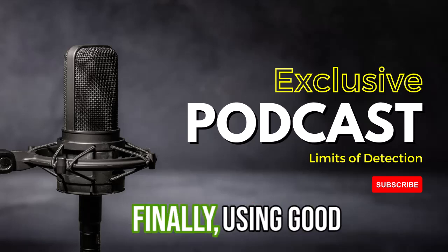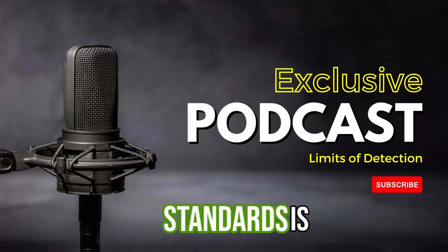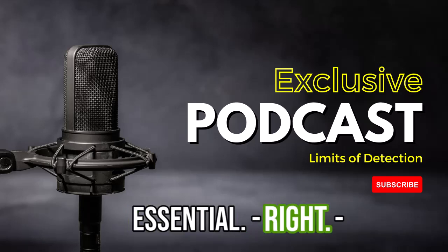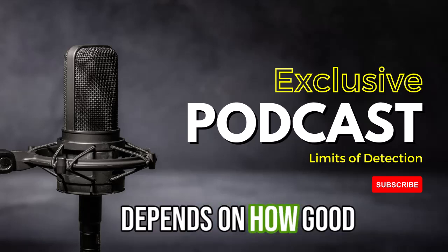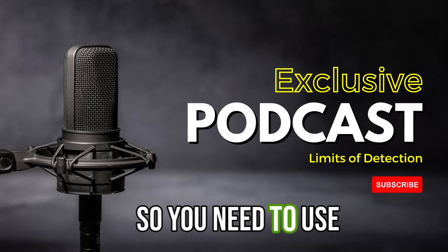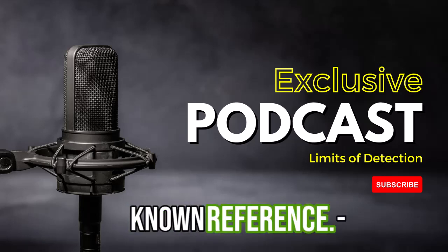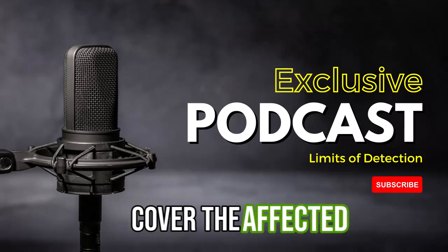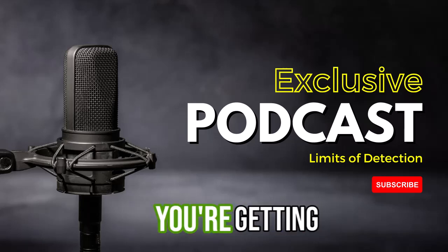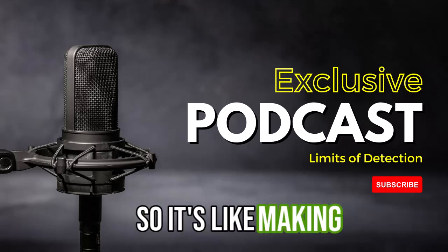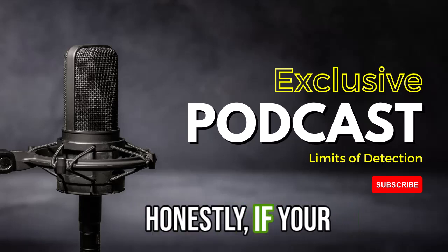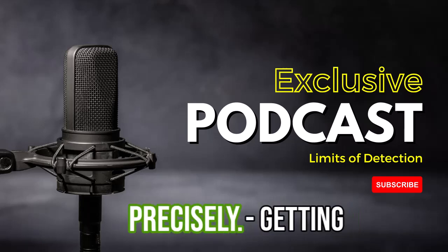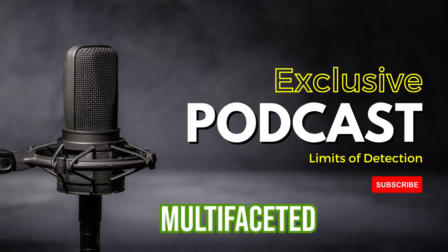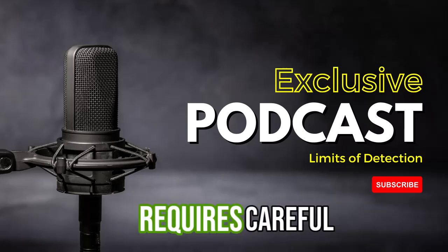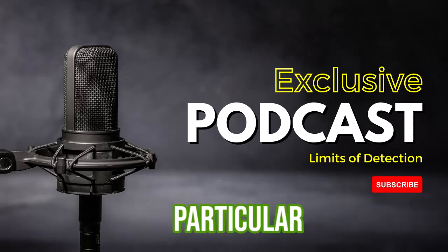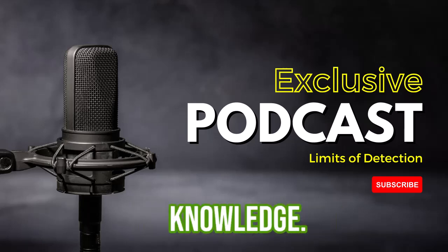Precisely. And finally, using good calibration standards is essential. The accuracy of your LOD really depends on how good those standards are. So you need to use standards that are traceable to a known reference and that cover the expected concentration range. This ensures you're getting reliable results. So it's like making sure your measuring stick is accurate. Exactly. If your standards are off, everything's going to be wrong. Precisely. Getting a low LOD is a multifaceted challenge. It requires careful planning, meticulous execution, robust data analysis.